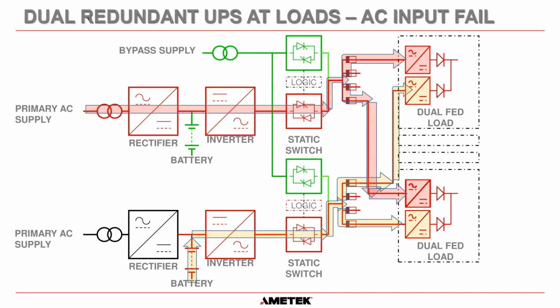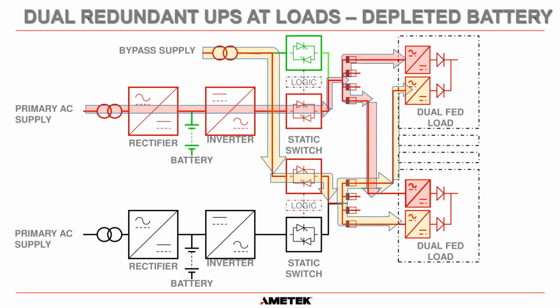Okay. And if we have an AC input failure on UPS A, the rectifier turns off, but the battery is going to continue to supply power to the inverter, and it will supply power to all of its loads this way here. And then when that battery depletes and gets down to 105 volts, the inverter turns off. Okay. And this logic here is going to say, okay, wait a minute. Our inverter has failed, so that means I need to transfer to bypass. Bypass will come down through this static switch, and we will continue to feed bypass into these loads, and inverter B will continue to feed backed up power into the other loads. So it's quite a robust system.